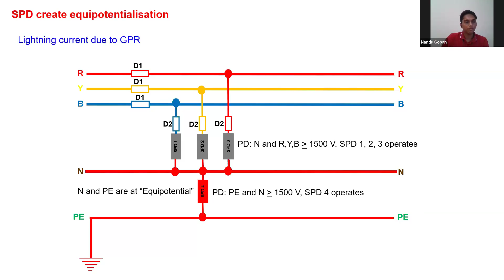Next, SPD 123 will be working, and RYB, neutral, and PE conductor will be in equal potential. That means the potential difference between all these four conductors will be equal, so there won't be any damage, insulation failure, or failure in the cables or the system, because all the lines are in the same potential. That is what SPD technically does. They actually make an equipotential bonding.